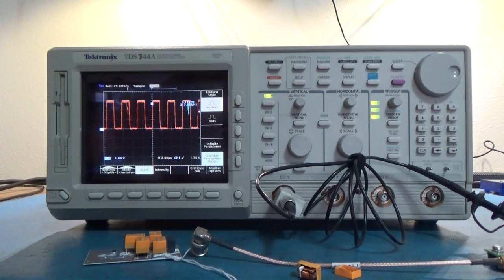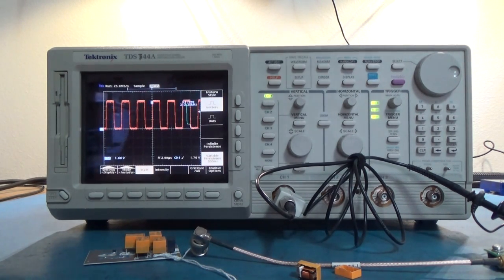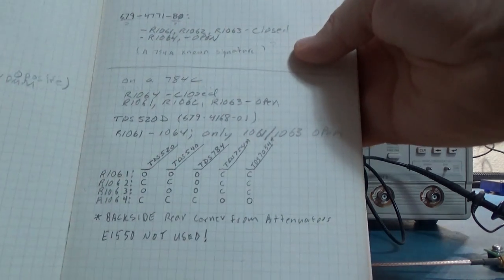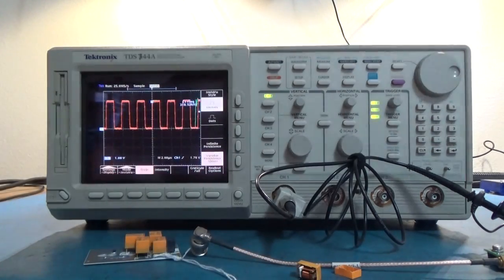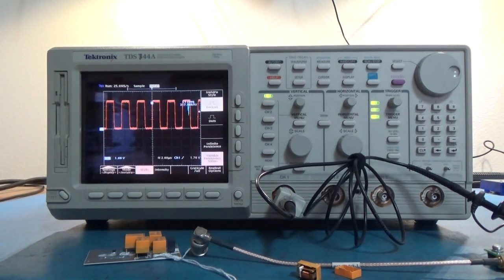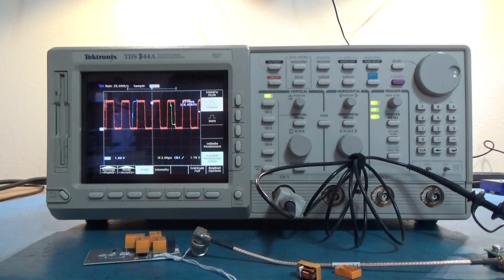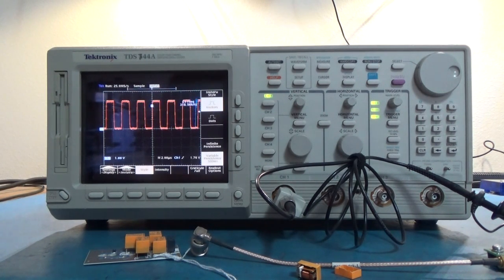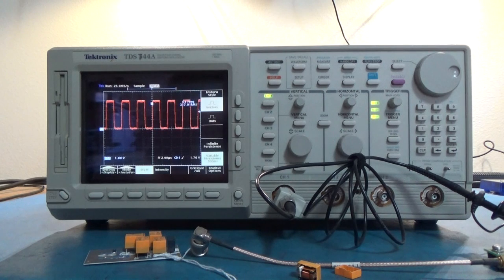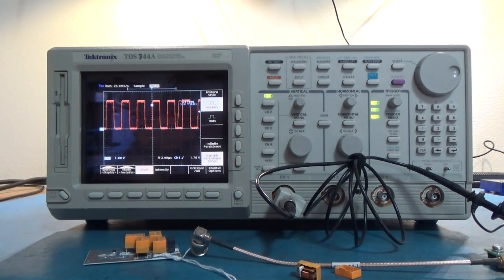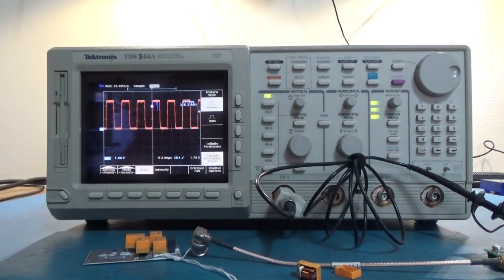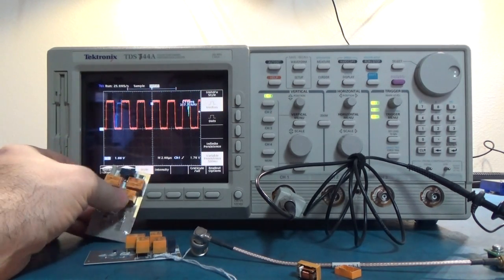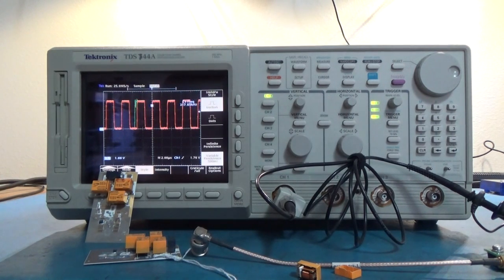If you took an acquisition board out of 540B, you could stick it in here. You could change two resistors, which this page, this book just glued you in on. Then now the scope thinks it's a 784. And a 784 will have a little more bandwidth than this scope currently has. But once you get out past 600 megahertz, you're probably going to have to calibrate the scope.